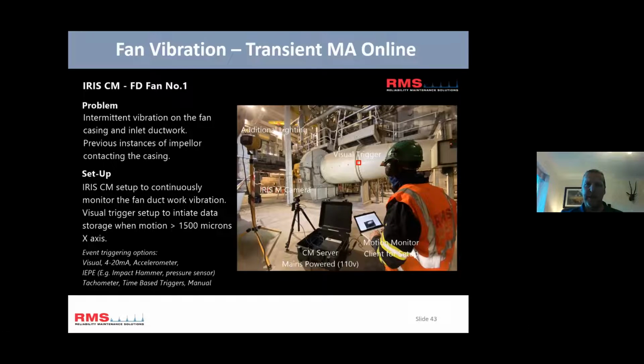It was in a boiler plant, on the FD fan for the boiler, and intermittently they were getting a noise coming from the fan, and they weren't sure what it was, and it was intermittent. Could you have a look? Could you use your camera? Well, it was intermittent, so we couldn't just sit there all the time.